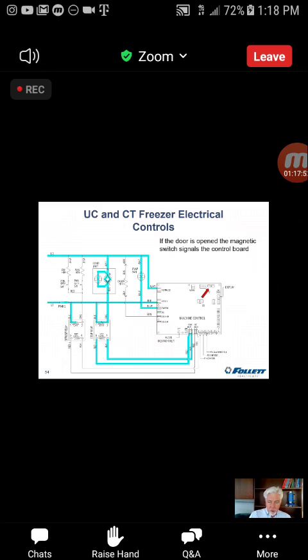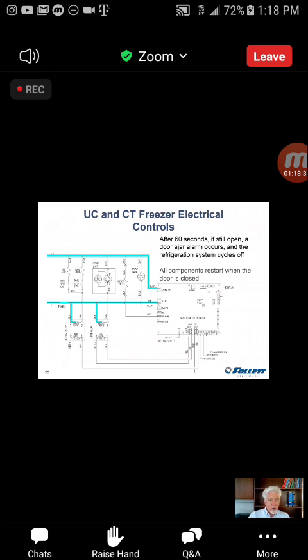Now, if at any time during regular running, remember the fan runs all the time unless we're in a defrost cycle, the door gets opened, the board detects that. It immediately shuts down the evaporator fan motor. So we're not going to be sending a whole bunch of very warm and humid air through the evaporator, which tends to lead to icing on the evaporator coil. So it shuts down the fan the entire time that the nurses have the door open. If they keep it open longer than 1 minute, you get the door ajar alarm and we shut down the refrigeration system. We don't want to keep running the compressor without that evaporator fan running. As soon as they reclose the door, everything restarts. We're not going to lock it out if they got a door ajar alarm.